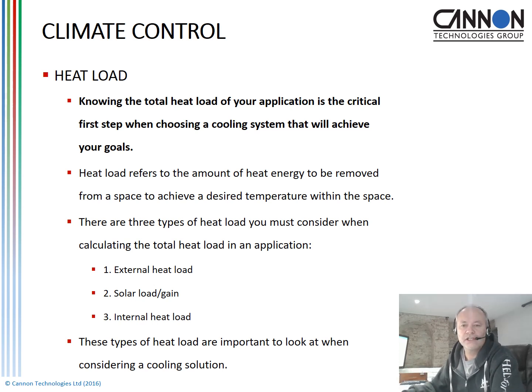When we're looking at thermal management, what we typically need to do is look at the types of heat load the particular application will have applied. That's the critical first step when choosing the cooling system and coming out with the right calculation for the goal we're trying to achieve. The heat load refers to the amount of energy that needs to be removed from the equipment chamber, and then the desired temperature at which we need to operate that equipment. There are three levels of heat load that we consider when calculating: the external heat load, the solar load, which is the heat from the sun, and then the internal heat load. These types of heat load are important to look at when considering the cooling or heating solution that's required.